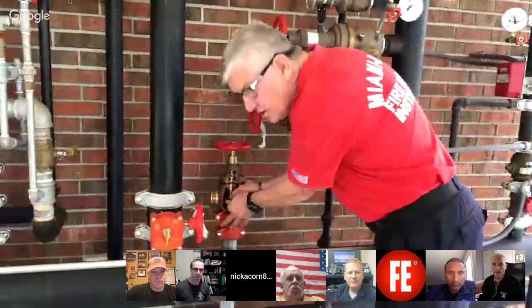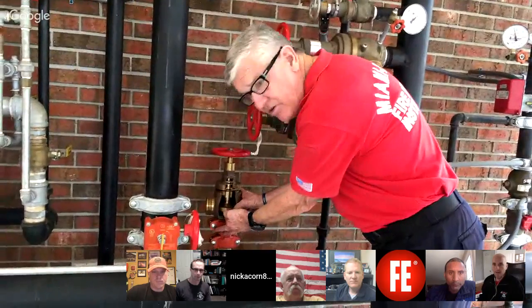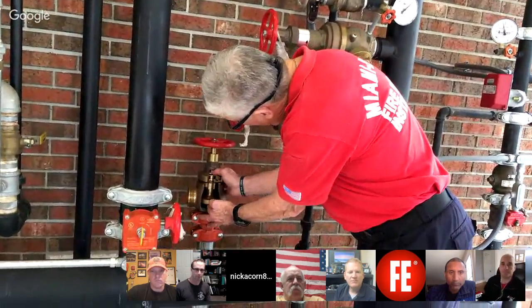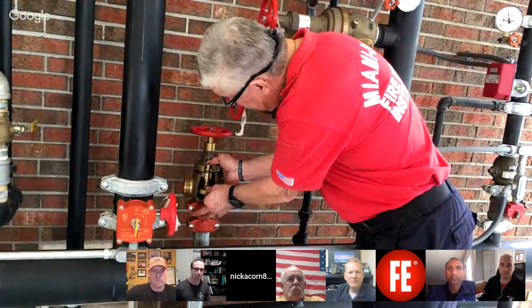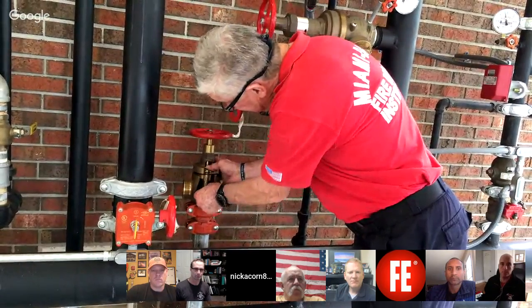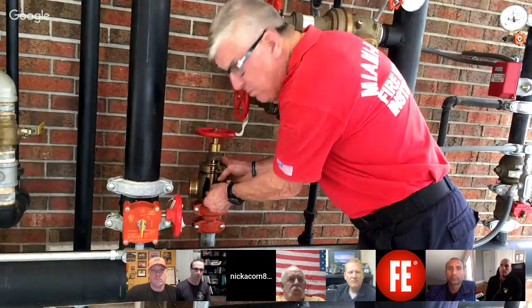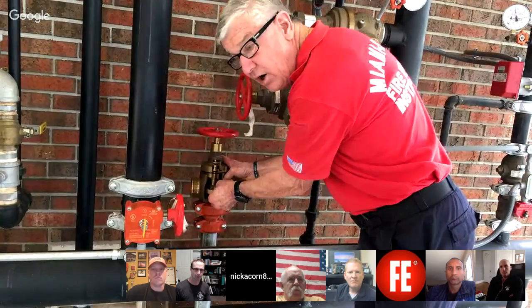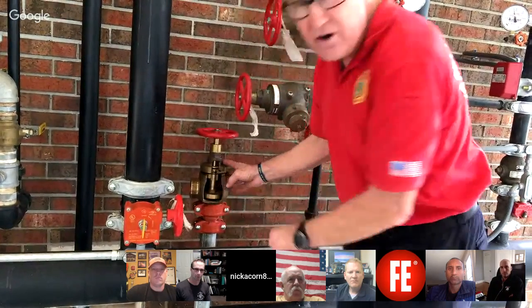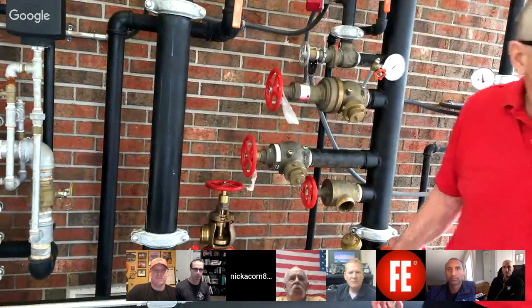Can you imagine? This is a PRV, a factory set PRV. Water acts upon this piston and pushes down this plunger like this. You have moving parts in here that are immersed in water. Can you imagine if you had a valve on your fire apparatus whose internal components were immersed in water and weren't flowed in 5 years, 10 years, 15, who knows how long? Right. Well, that's why we've added the valves above the deluge valve, so we can do a full operation of that valve.